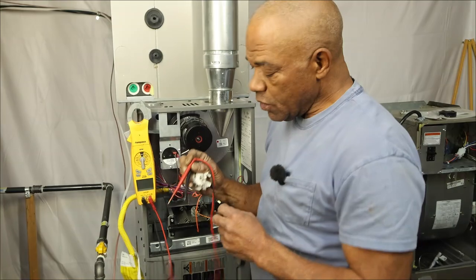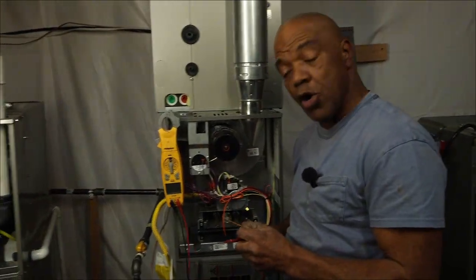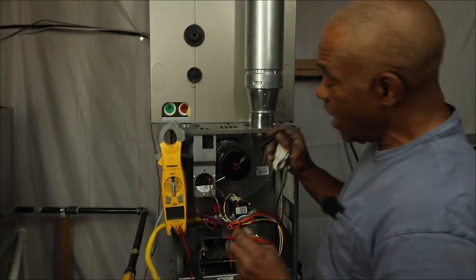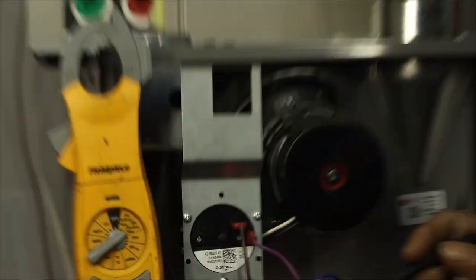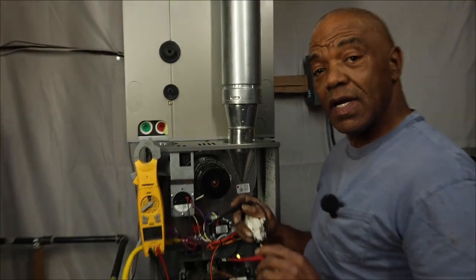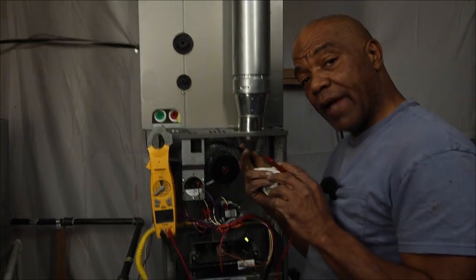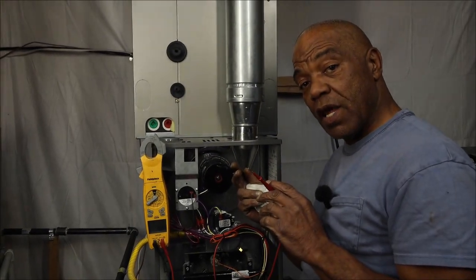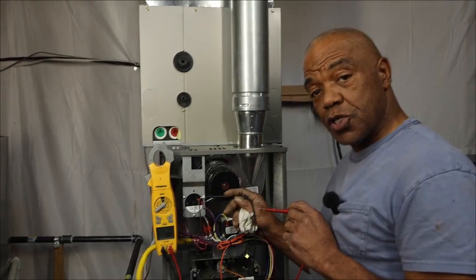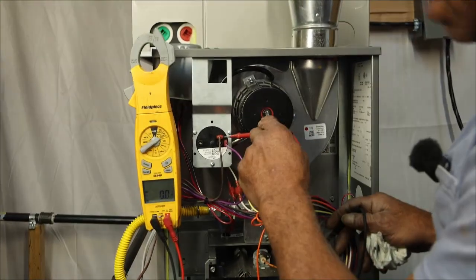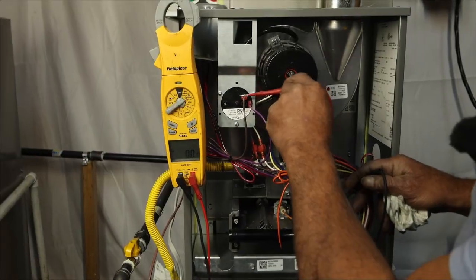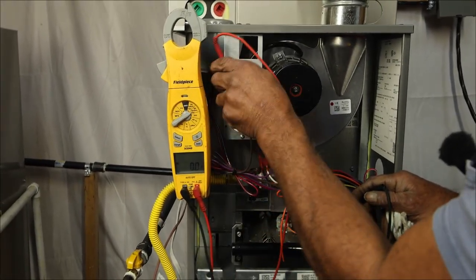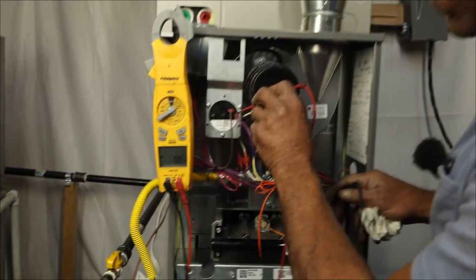All right. One of the other functions of my multimeter, my amp probe, is that I can check for power. So if I have components that are losing power, I can use my amp probe in order to trace that power. We're going to look at my pressure switch right here now, okay? Now, as I check my pressure switch, I'm going to look for power on the two different legs, okay? I've got two legs on my pressure switch.